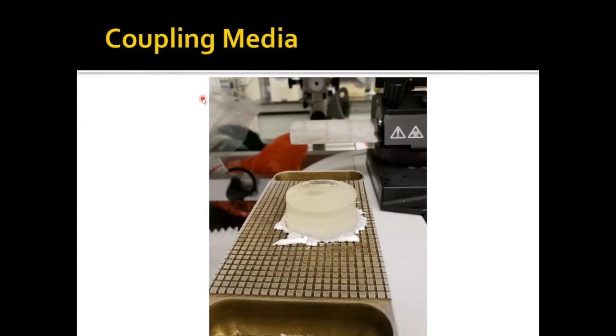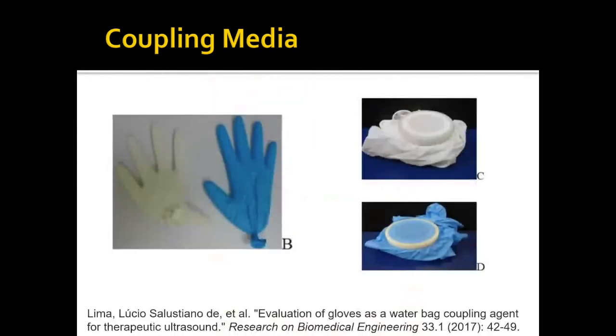This is our technique, and you can try this out in your lab, especially if you have a wet lab or some sort of precise cutting instrument. We purchased these Aquaflex gel pads, which are really massive—several centimeters high and almost 6 or 7 centimeters in diameter. So just using them as is not ideal. What we do is mount them in a microtome, freeze the bottom so that it sticks, and then use the blade to cut very thin sections of about 1 to 2 millimeters. We cut a lot of them, keep them in the fridge, and use them as quickly as possible within a few days to prevent air diffusion and air bubbles. That's worked for us quite well.